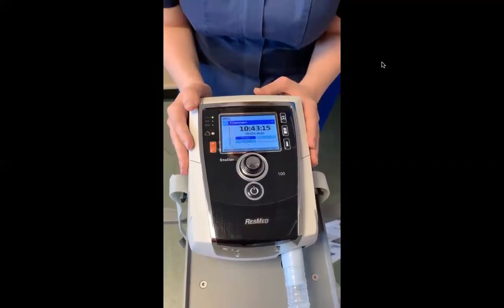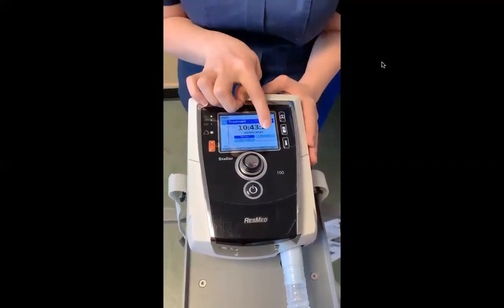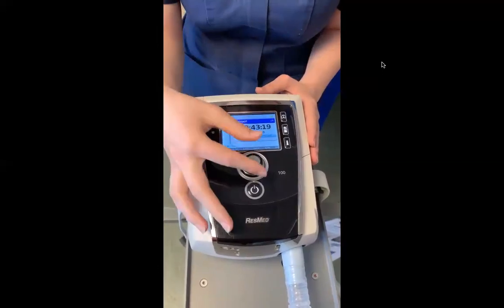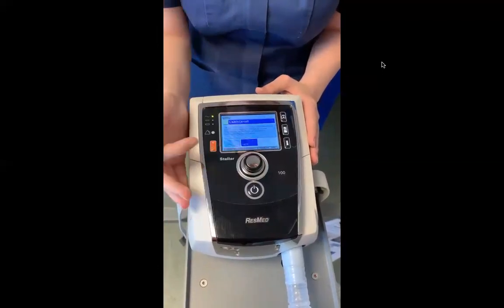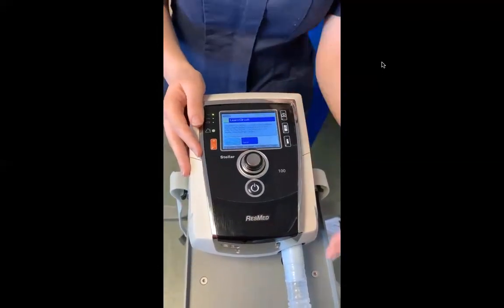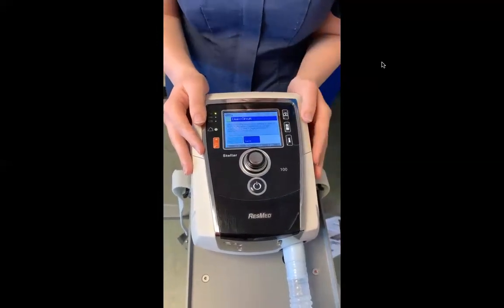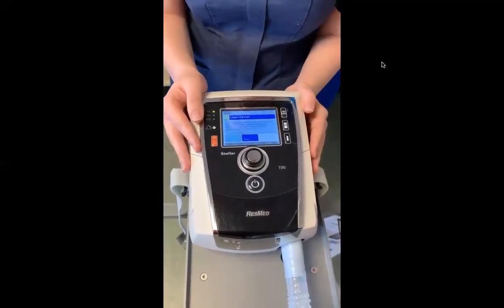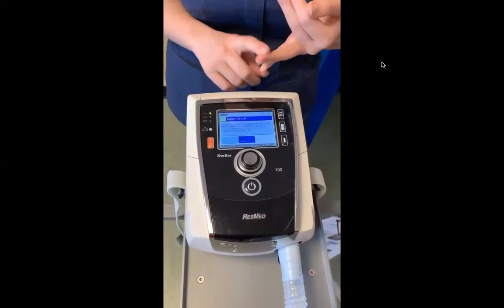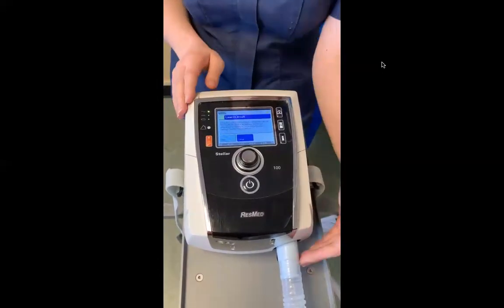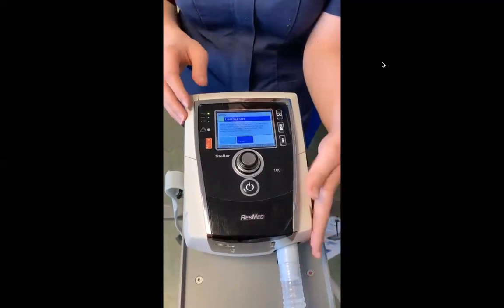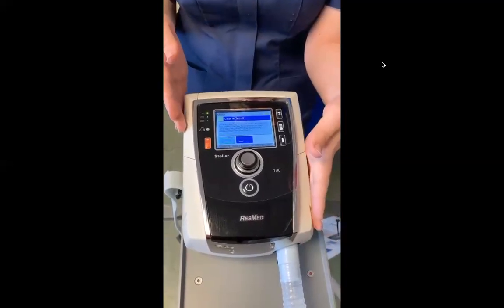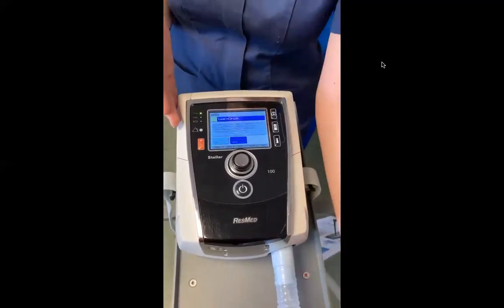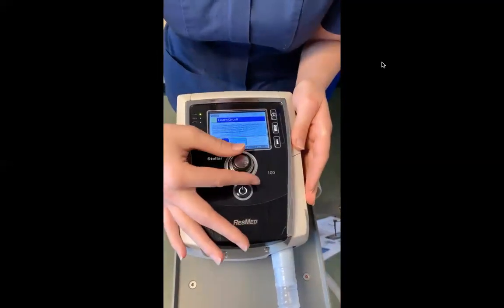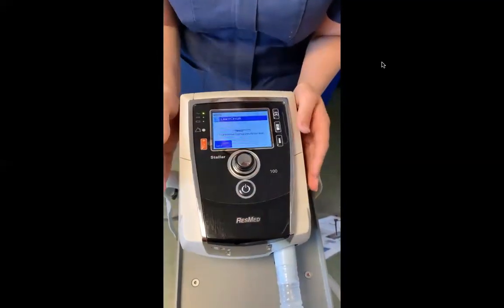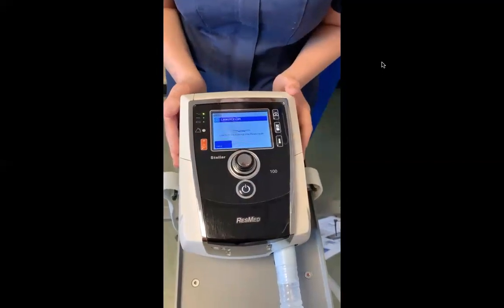So when you come to the home page, you have a ramp, a face mask and a learn circuit. The most important thing to do first is your learn circuit. Your equipment needs to be set up with the face mask and the HME filter, because the learn circuit not only tests if it's safe to use, it also checks for the dead space. So then you know that the ventilation observations you're getting are just from the patient and it's nothing regarding the ventilation tubing. All you have to press is start. It's very easy.